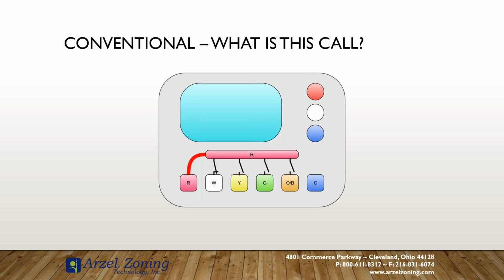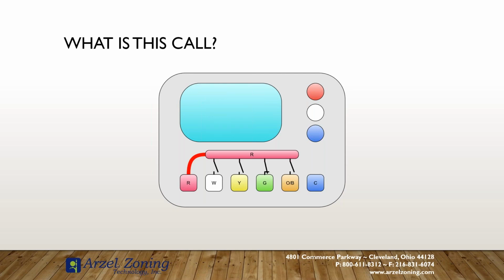I have a switch that's closed. What does this call if I have a conventional system? Heating. It is a call for heating. How about now? What's this call? This is a cooling call. Correct. This one's pretty simple. Fan call. The G contact is closed.